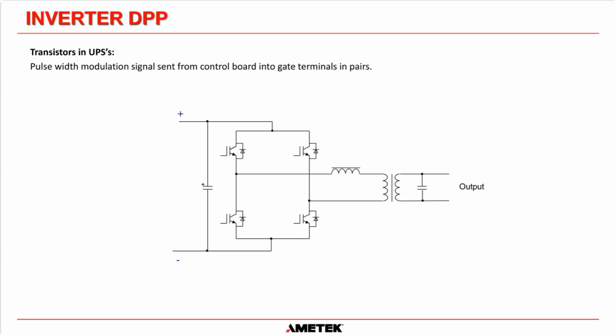The problem with a 10 amp breaker is that it can take up to 5 to 10 times the required current to trip that breaker very quickly. So if you have a short circuit on one of those breakers, you would like the inverter bridge to be able to supply that large amount of current to that particular circuit so that breaker will trip and none of the other circuits on that AC panel will trip, and that the voltage doesn't dip in such a way that it causes the other loads connected to that AC panel to be affected.